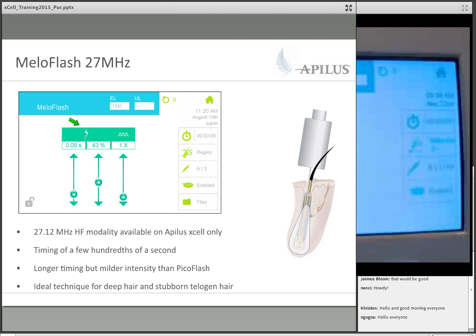And we have MeloFlash. If you look at your time and your intensity, MeloFlash is in hundredths of a second, so 2 spots after the decimal. And my percent is what we call medium intensity, which is between 40 to 60%. So the timing is longer, the intensity is a little bit lower. What that does is it allows for a little bit more spread of the current, so a bit of a wider treatment area. My teardrop pattern is a little bit fatter than it was with the Picoflash.